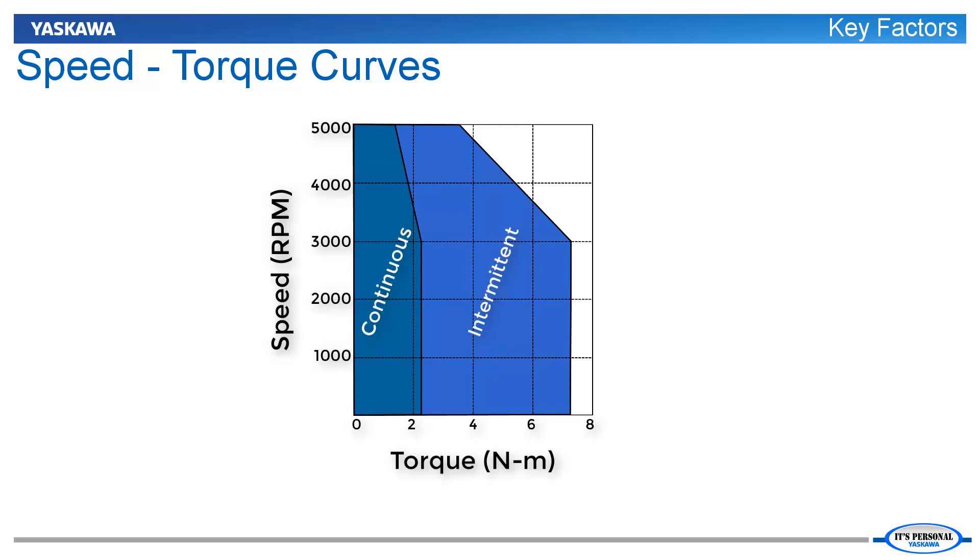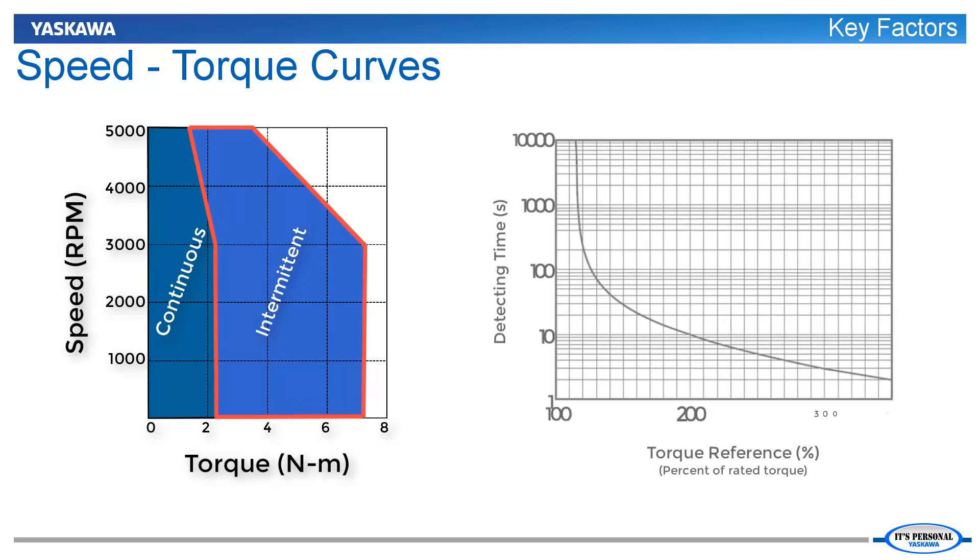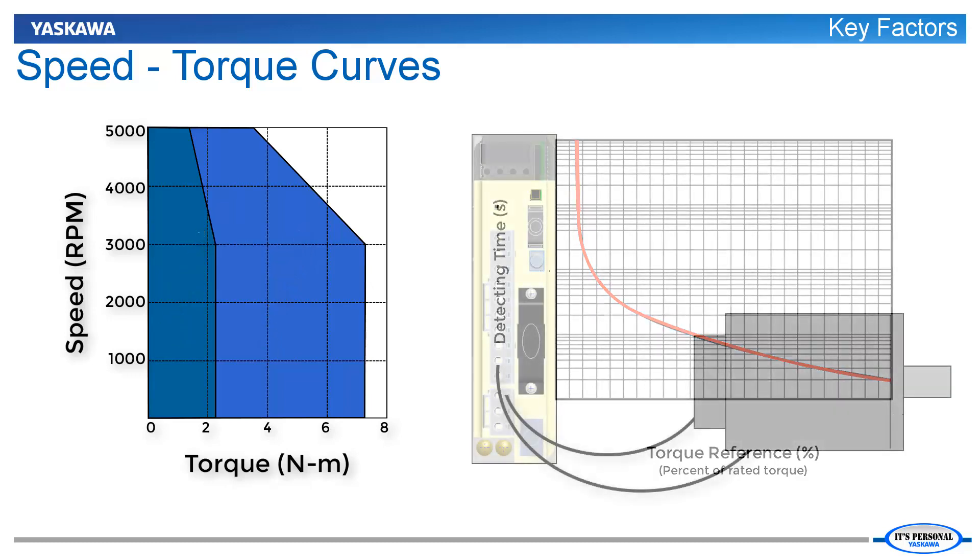If the combination of torque and speed required by the motor is found in the continuous region, then the motor can produce that torque and speed forever without any chance of overheating the motor. If the combination of torque and speed produced falls in the intermittent region, then the motor can only produce that speed and torque for a limited amount of time. If that time is exceeded, the motor will begin to overheat.